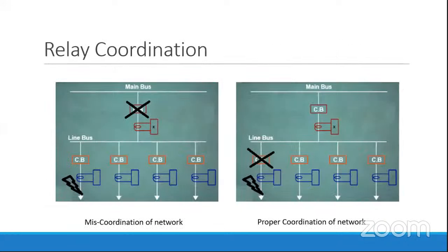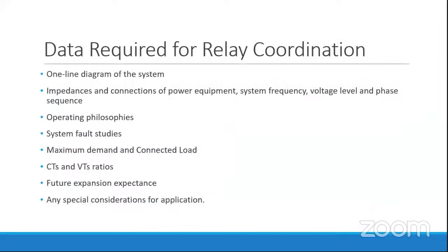So for relay coordination, we need certain data to coordinate our network. The data required for relay coordination starts with a single line diagram of the system. If we need to coordinate any network, we need to know the entire network from downstream to upstream. For this, we need a single line diagram.